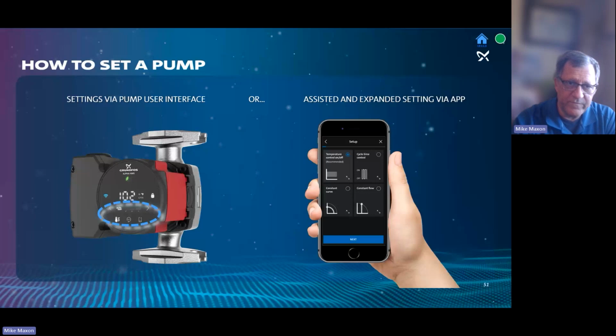Those are for if the pump is in a hot garage and you want to have the pump turn on at 100 degrees fluid temperature. I know my garage can be 100 degrees in the summer, so that pump would never turn on. So we'll have a fallback. So we'll say, okay, no matter what the temperature of fluid is, turn on after 20, 30 minutes, whatever that might be.